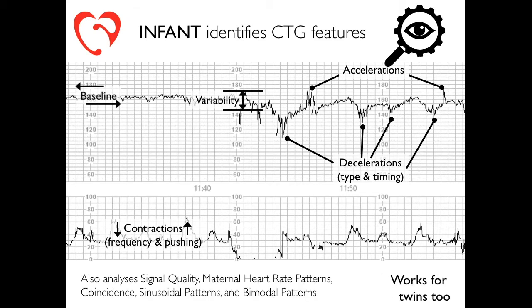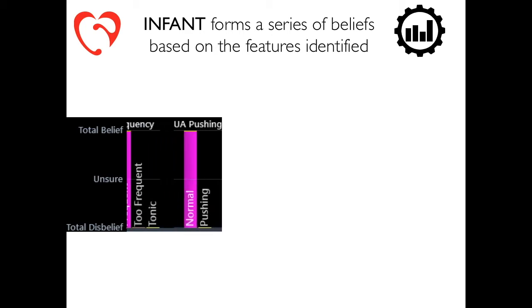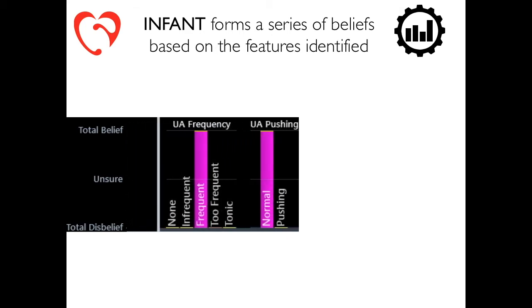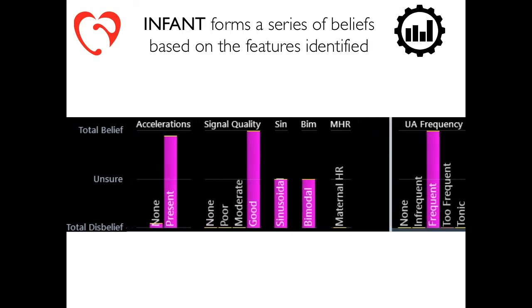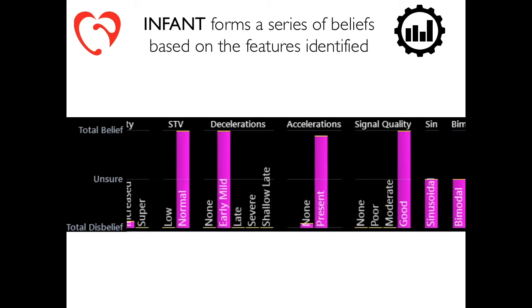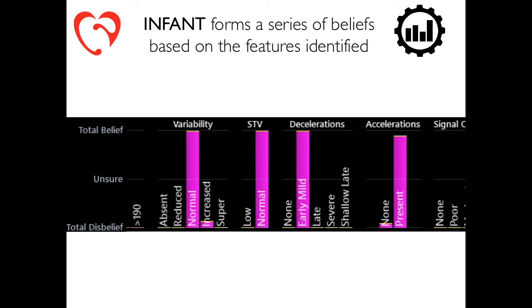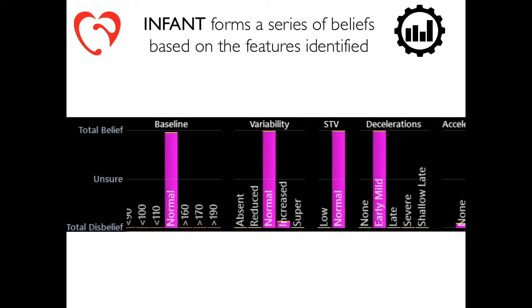INFANT can analyse two heart rate channels at the same time, so it also works for twins. INFANT identifies every feature on the CTG and then builds a picture of what the trace shows via an ever-changing histogram, one per feature. Every feature detected adds some weight of belief that a certain classification has been reached.